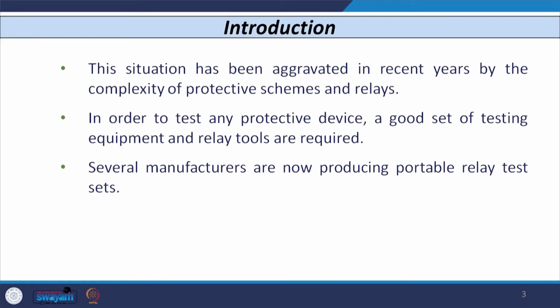very small. If I consider one relay and let us say the lifespan of that device is 10 years, then within this 10-year span this device may operate hardly 10 or 20 times. For the rest of the period this device does not operate. So, it is very important as far as a protective relay is concerned that it has to operate only in case of fault conditions, and it cannot operate in normal condition when there is no fault, or in an abnormal condition when there is an external fault. So, it cannot be readily tested under normal operating conditions.